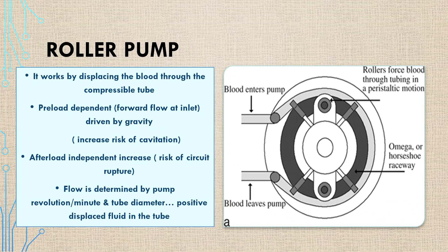The roller pump works by squeezing blood through compressible tubes; rollers force the blood through peristaltic motion to the other side. It is preload dependent, driven by gravity. As a result, decreased preload in hypovolemia or hemorrhage increases risk of cavitation. It is afterload independent, meaning there is risk of circuit rupture in case of hypertension. Flow is determined by pump revolutions per minute and tube diameter.